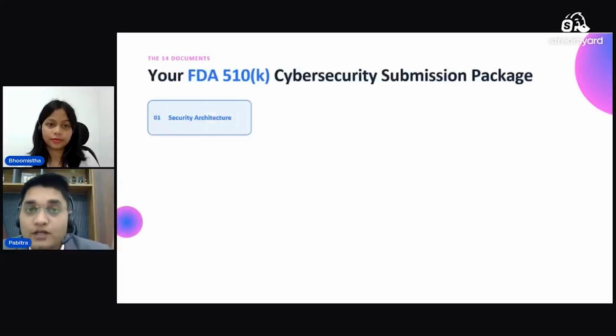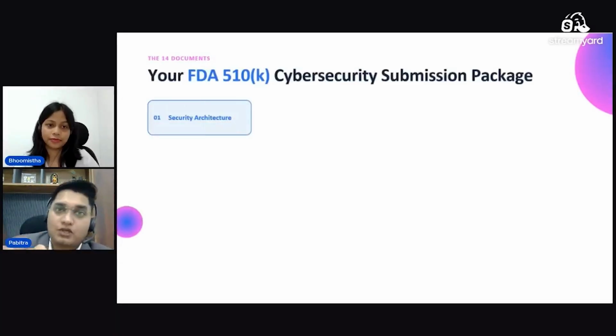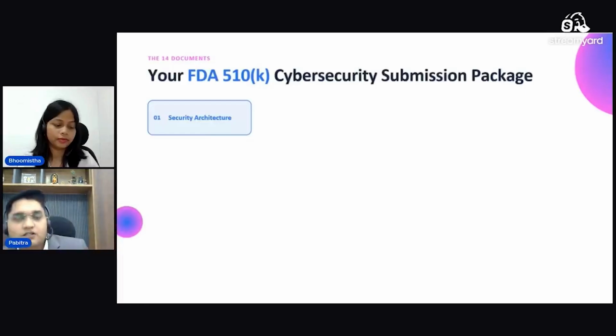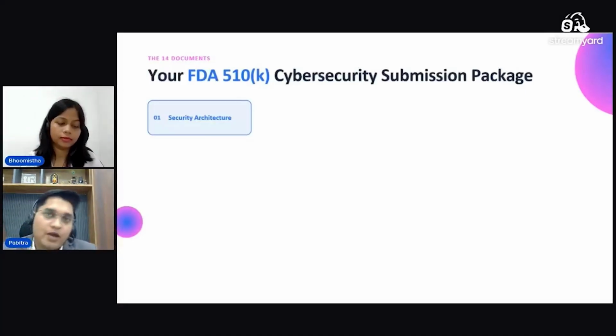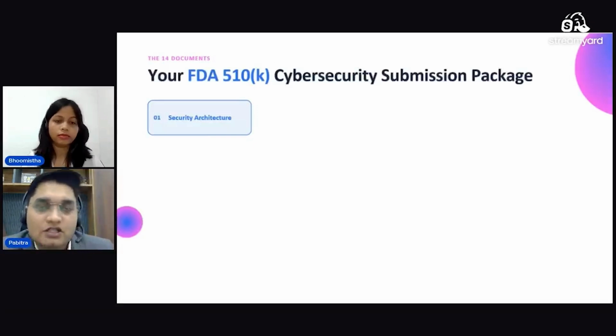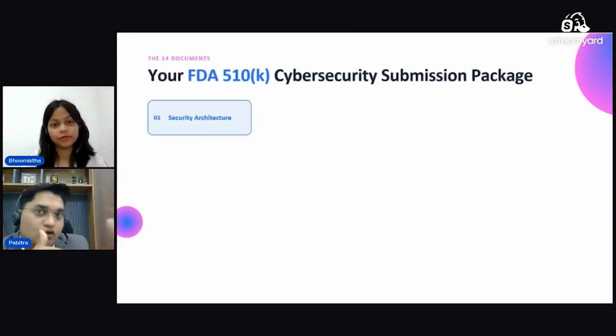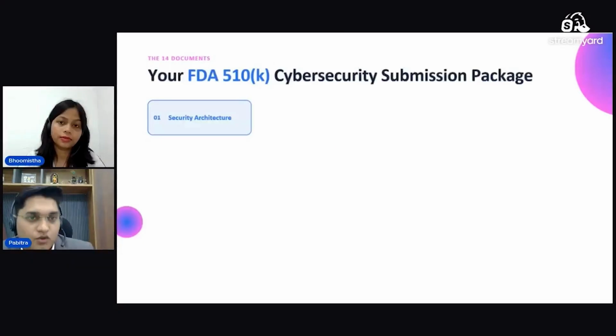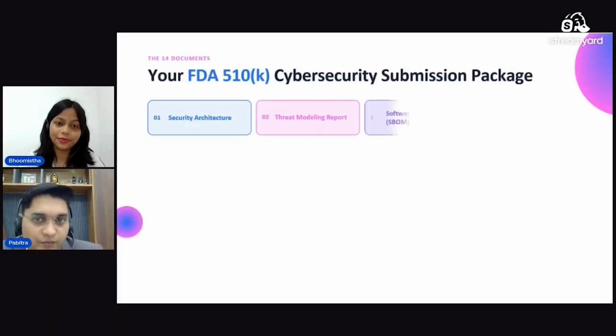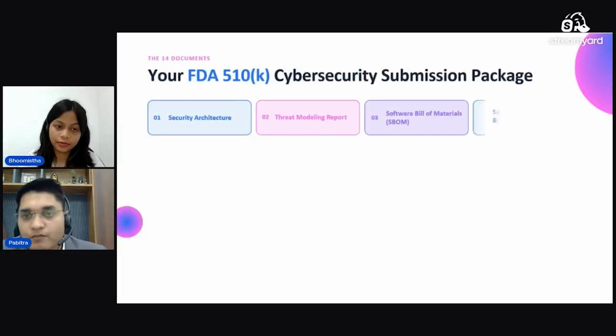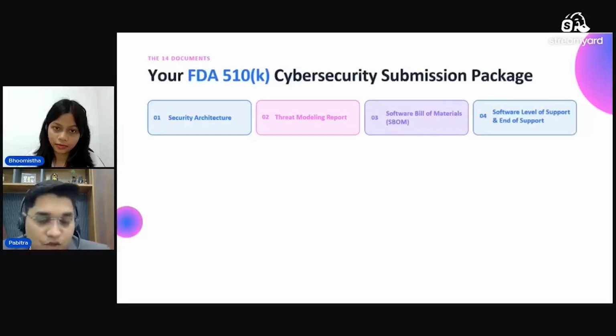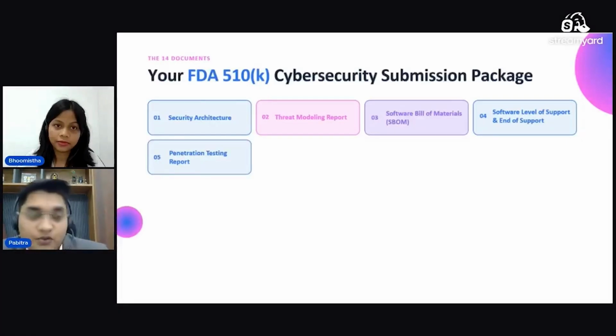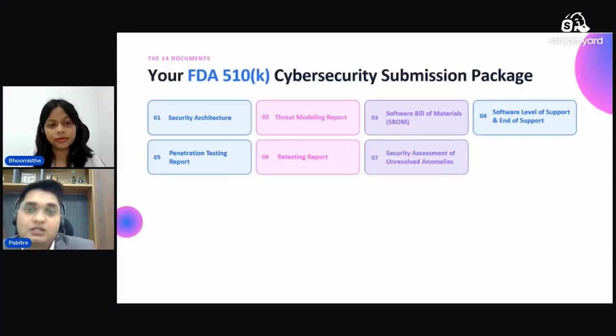First, security architecture review. You have your architecture, but you have to do a security architecture review. I'll list out all these 14 documents, then we'll jump into them one by one and understand what exactly needs to be created in each document and what exactly the FDA is looking for. So first is the security architecture report, the threat modeling report, the software bill of materials report, which is called SBOM, and the software level of support and end of support report, which is very new. The pentesting report is mandatory and essential for proof and traceability. If you conduct the pentest, then the retest report, and there is a security assessment of unresolved anomalies, right?